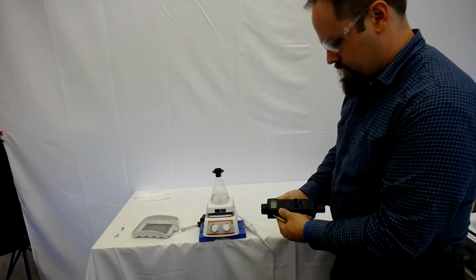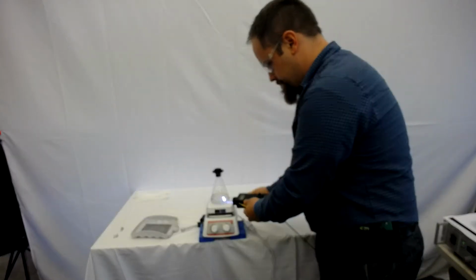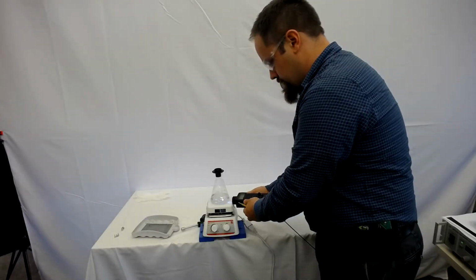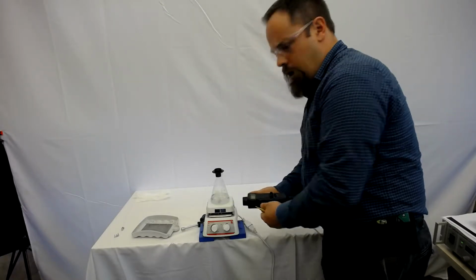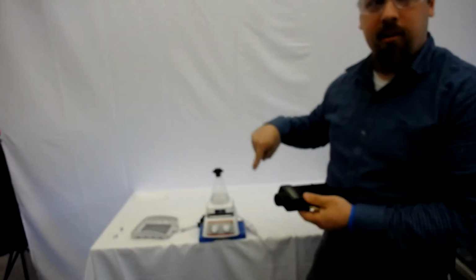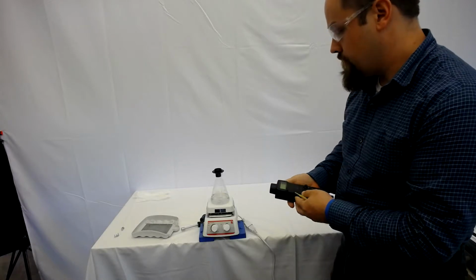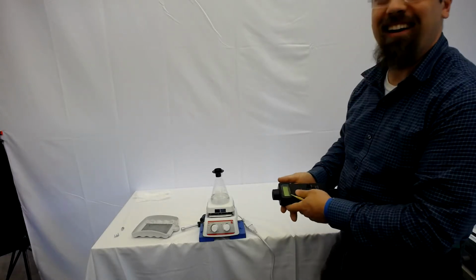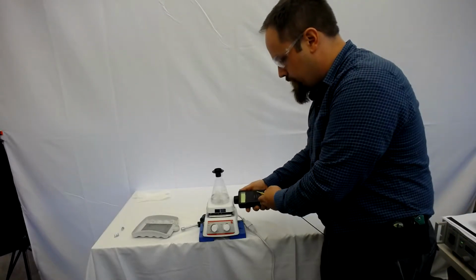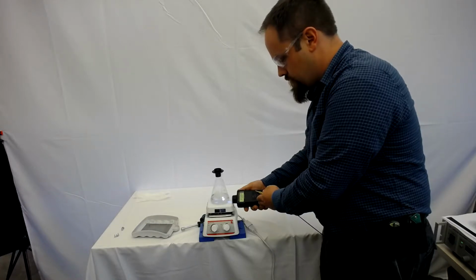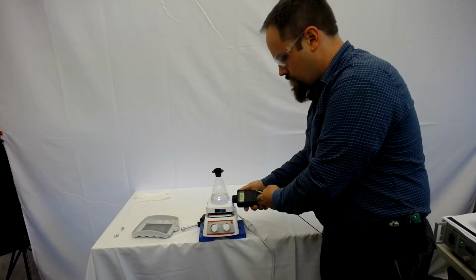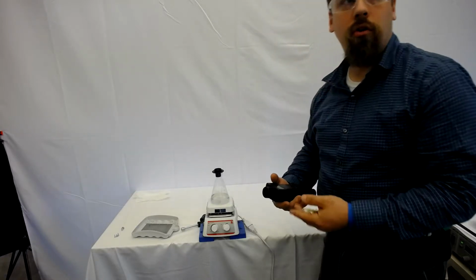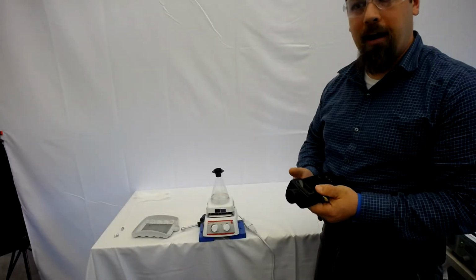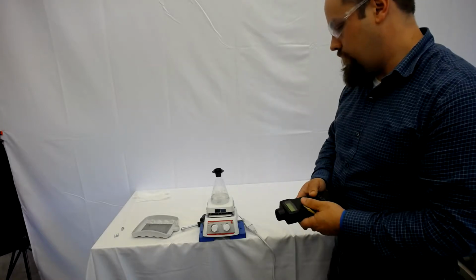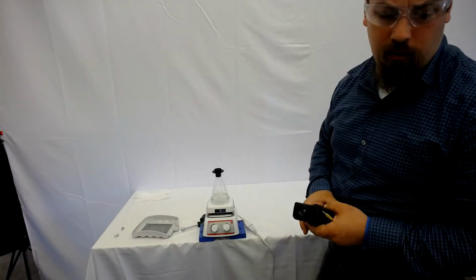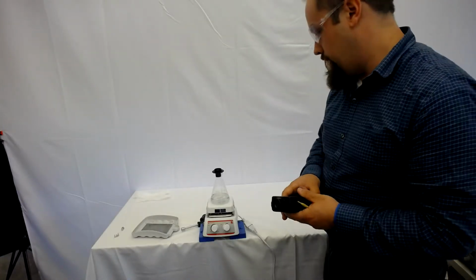And then we're going to use our phototachometer. Take a speed. When we use the phototachometer on this, it's actually capturing 2 cycles per rotation. So it's actually half what is shown on the screen of the phototachometer. So right off the phototachometer, this is around 250 RPM. So we are at about 125 RPM on the unit. That's great. What we're looking for is between 50 RPM and 250 RPM.